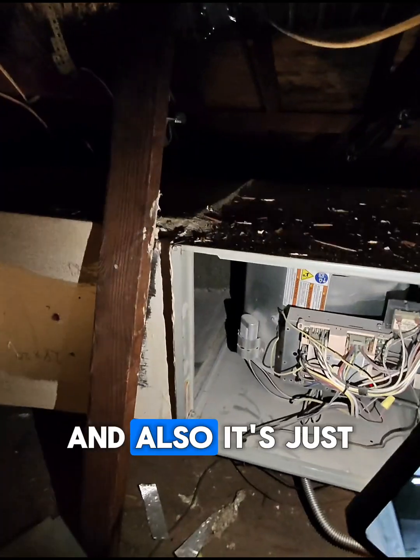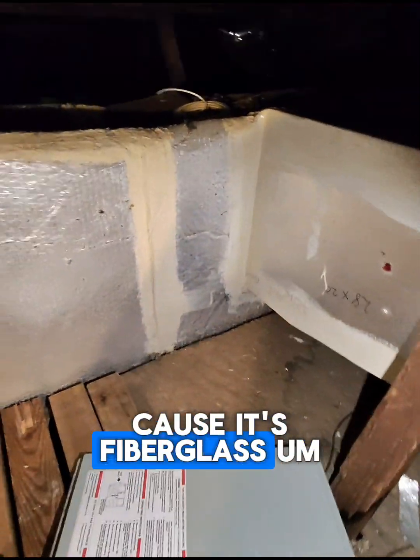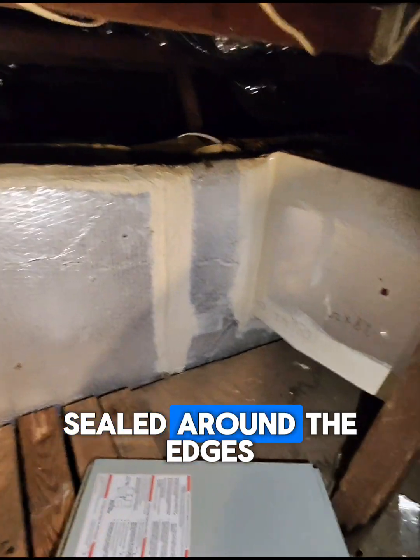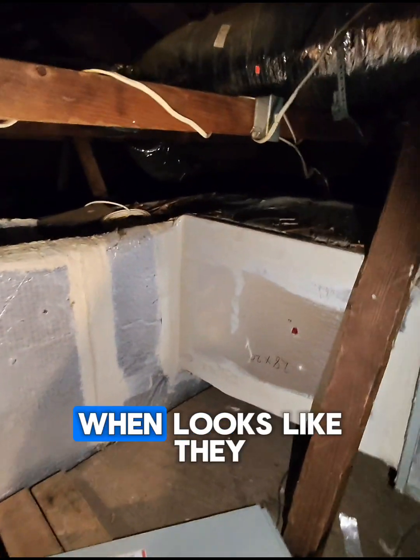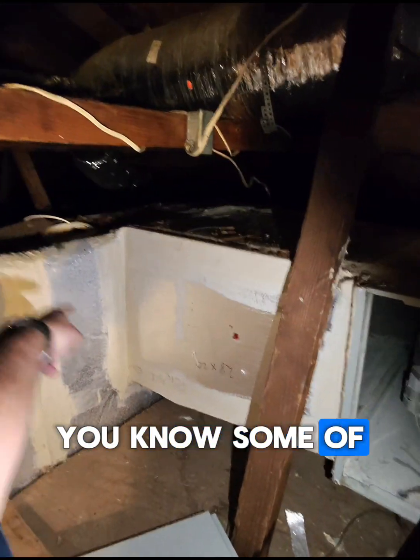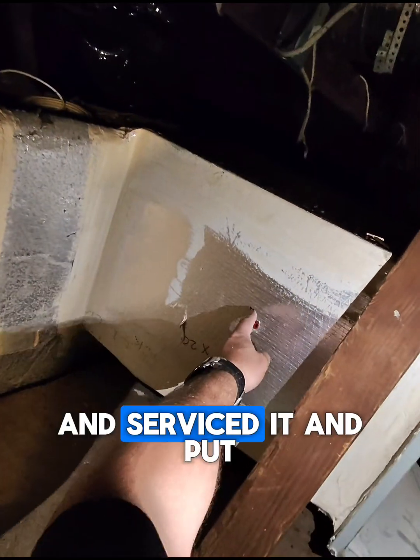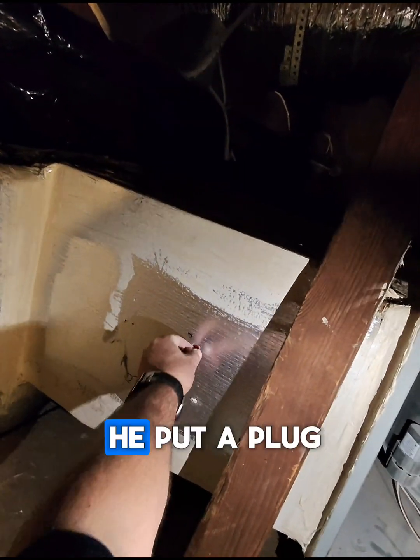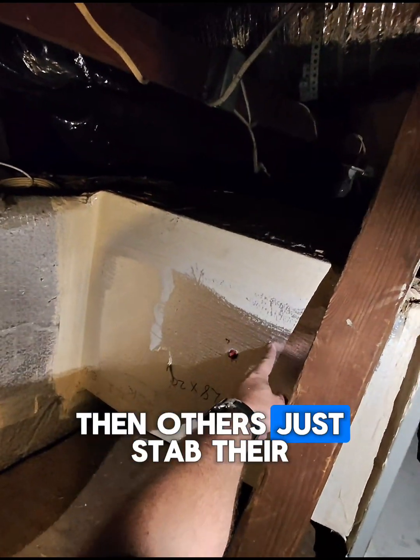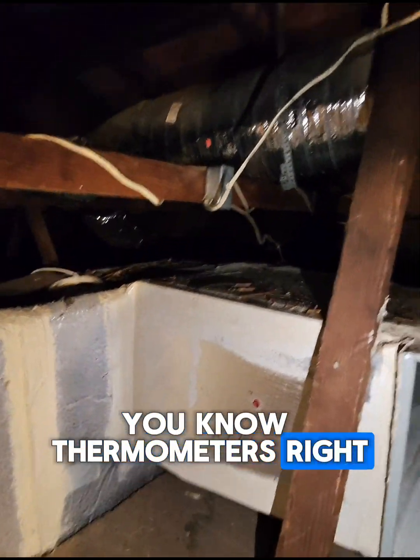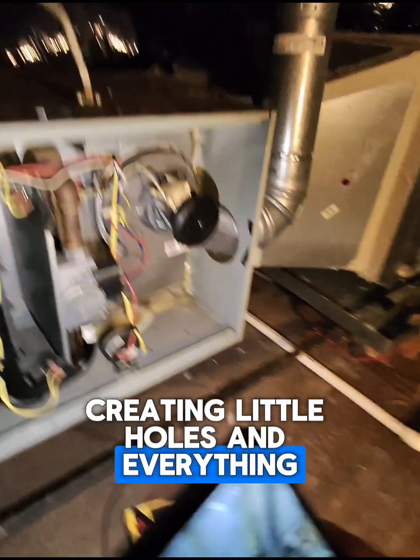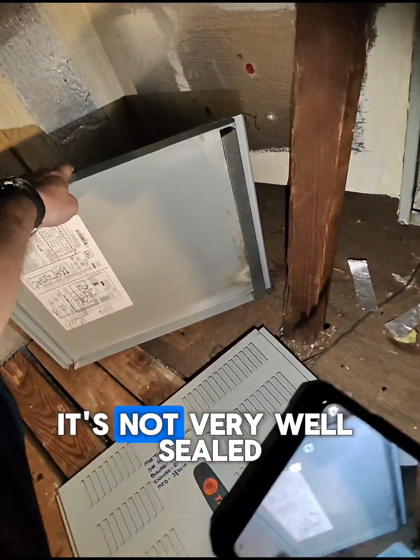And also it's just kind of an irritant because it's fiberglass, and then it was never really that well sealed around the edges, way back when. Looks like they did go around some of these joints with some mastic airlock, but you've got people that have come in and serviced it and put real big holes. He put a plug, which is good, but then others just stab their thermometers right into your ductwork, creating little holes and everything. And then the equipment itself doesn't help because, as we can see, it's not very well sealed.